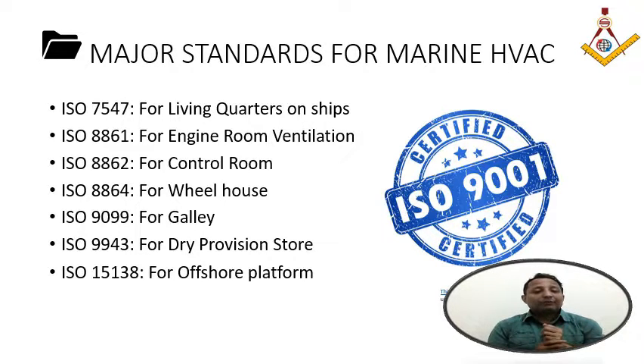First is ISO 7547 for living quarters on ships or vessels. Suppose we have to design an FPSO, a passenger ship, or a cruise ship - this is a very important standard. It talks about the pressure requirement, how much it should be as compared to the total air supply, and the minimum number of air changes in the toilet, galley, laundry, smoking area, and recreation area.